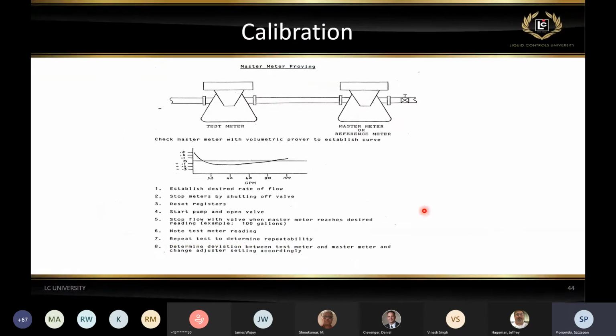The third method that is fairly common in certain parts of the world is master meter proving, when a meter of a known curve, of a known performance, is used as a reference device. So you're really testing a meter against another meter, and that meter is of a known performance. So you know what the percentage errors are at specific flow rates. And again, the process is very similar. You're comparing the value of the tested meter to the master meter.